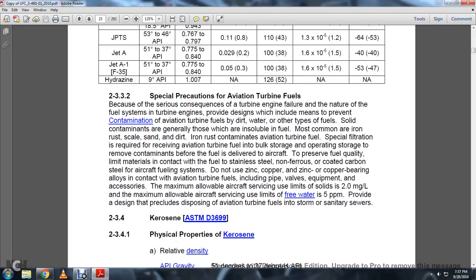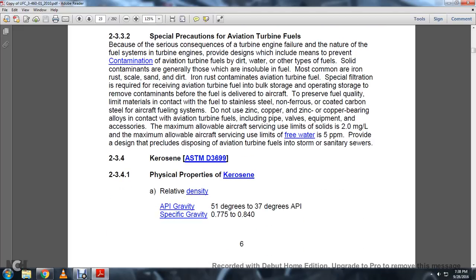Iron rust contamination of aviation turbine fuel requires special filtration when receiving the aviation turbine fuel into bulk storage and operating storage, removing contaminants before fuel is delivered to the aircraft to preserve the fuel quality. Materials in contact with the fuel should be stainless steel and non-ferrous, or coated carbon steel, in the aircraft fueling system. Do not use zinc or copper-bearing alloys in contact with aviation turbine fuels, including piping, valves, and equipment accessories. The maximum allowable aircraft servicing limit of solids is 2.0 milligrams per liter, and the maximum allowable aircraft servicing limit of free water is 5 ppm. Provide a design that precludes disposing of aviation turbine fuels in storm and sanitary sewers.